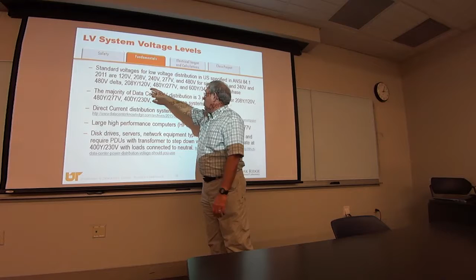Now in the computer world, you usually got, well here's all of them: 120 volt single, 208 volt single, 240 volt, 277 volt single, 480 volt single. And then you got 240 volt and 480 volt delta, 208, 120 Y, 480 volt Y, 600 Y. Those are the kind of voltages you can have.